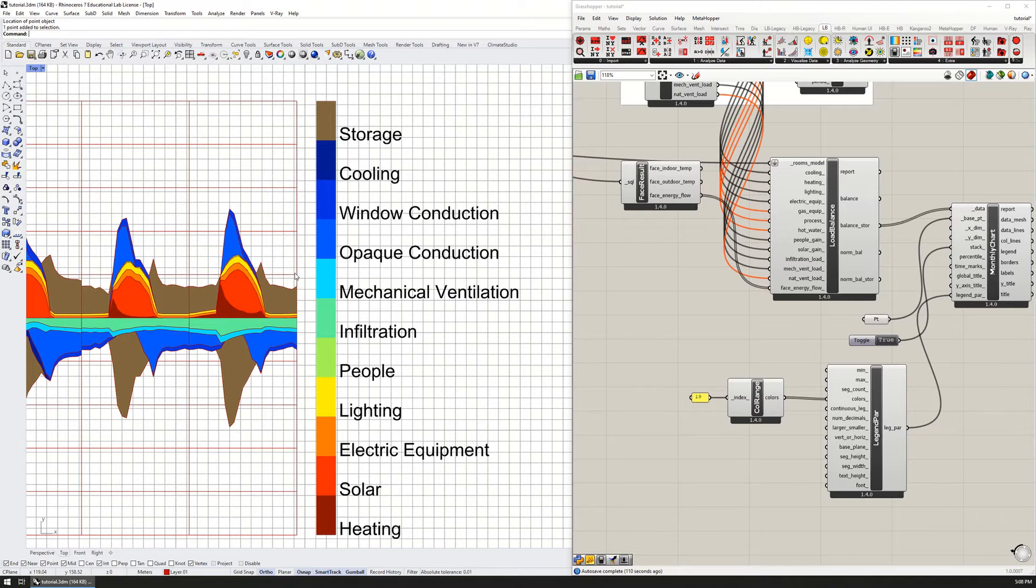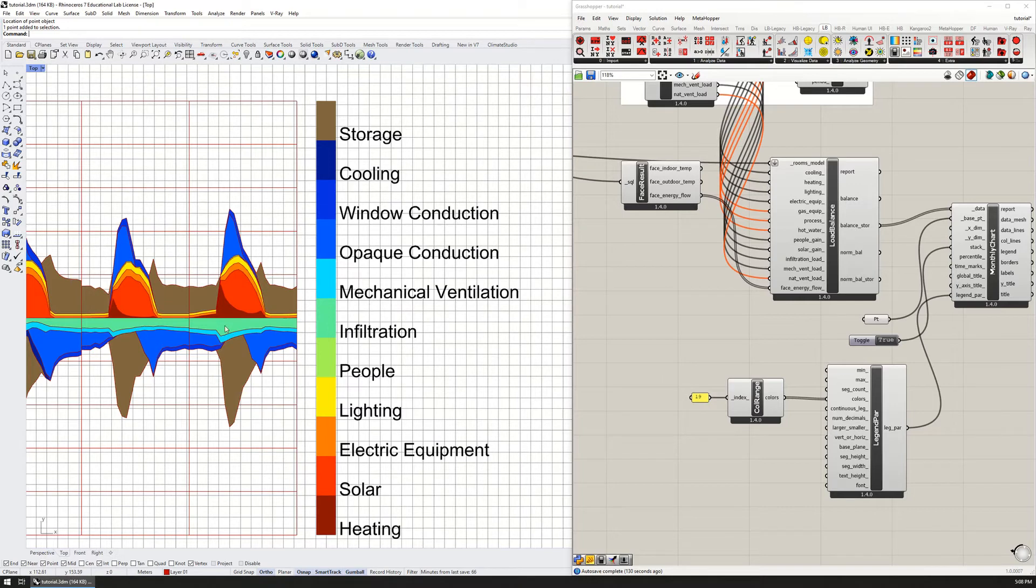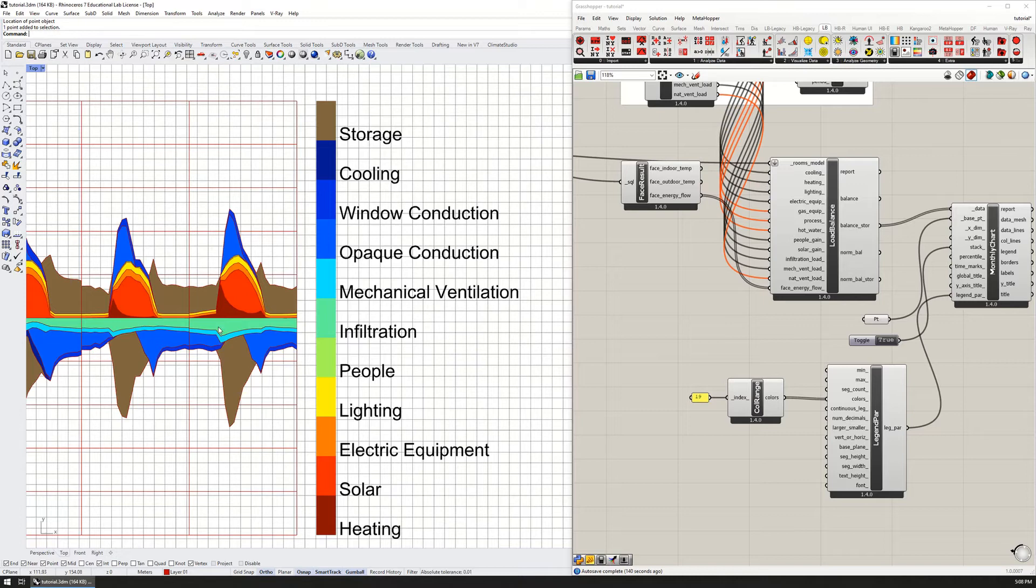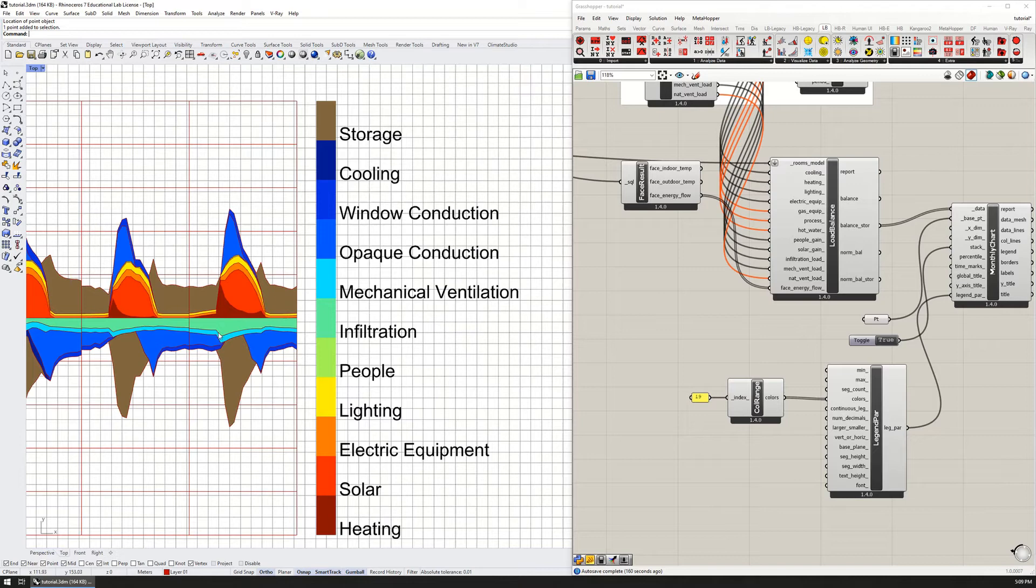This is a really nice way of starting to diagnose what parts of your building you might want to target in order to reduce energy use. The energy being used here is the heating, which is being used all day, especially in the morning, and then the equipment and lighting of course is also part of it. But if we're going to reduce the heating, I'd say the first thing that we should probably target is the opaque conduction, these losses that we're getting right here, as well as the infiltration right here. We can address the opaque conduction with insulation in the exterior envelope, we can address the infiltration by changing that as an interior load.